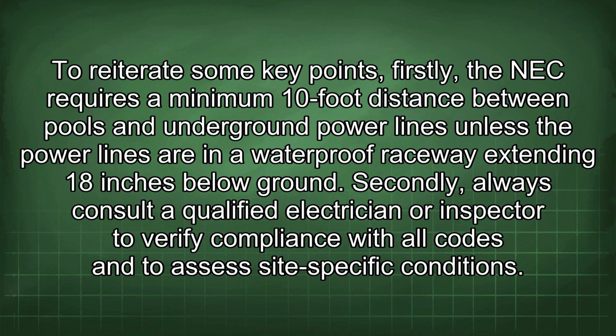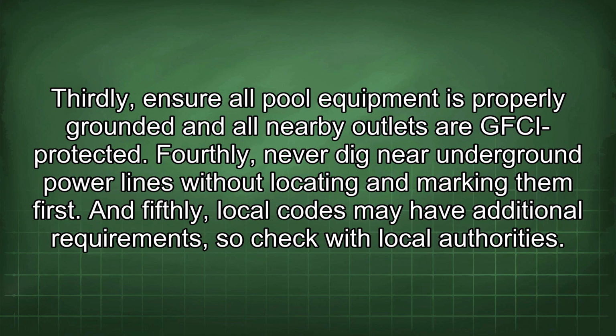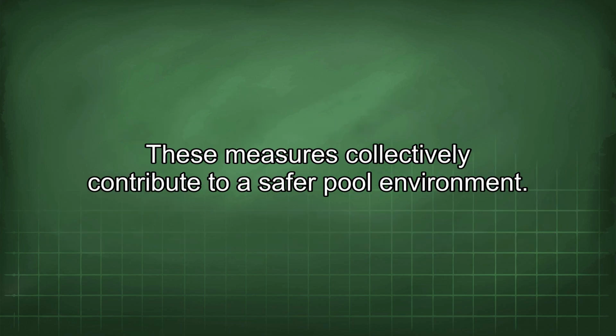To reiterate some key points, firstly, the NEC requires a minimum 10-foot distance between pools and underground power lines unless the power lines are in a waterproof raceway extending 18 inches below ground. Secondly, always consult a qualified electrician or inspector to verify compliance with all codes and to assess site-specific conditions. Thirdly, ensure all pool equipment is properly grounded and all nearby outlets are GFCI protected. Fourthly, never dig near underground power lines without locating and marking them first. And fifthly, local codes may have additional requirements, so check with local authorities. These measures collectively contribute to a safer pool environment.